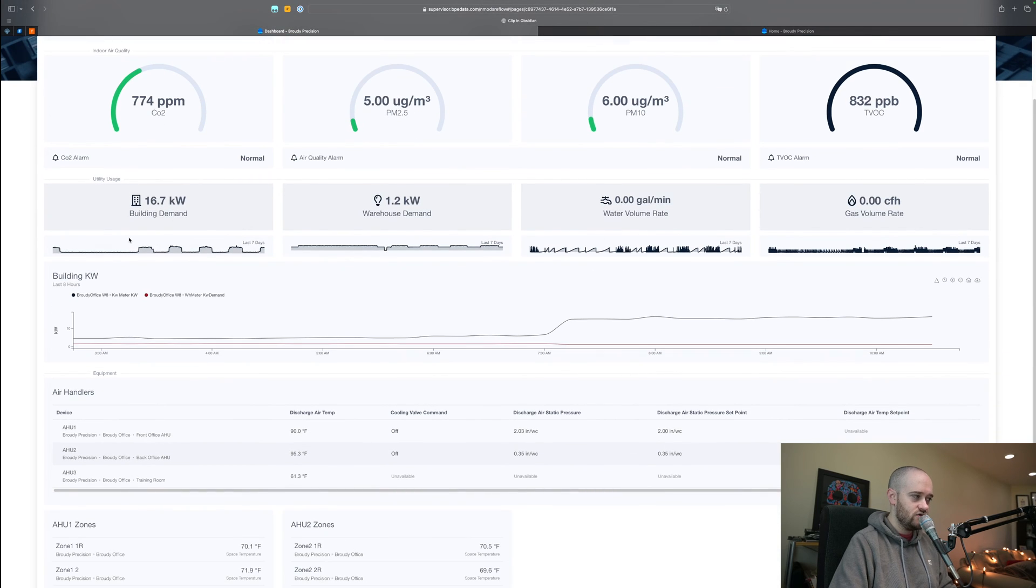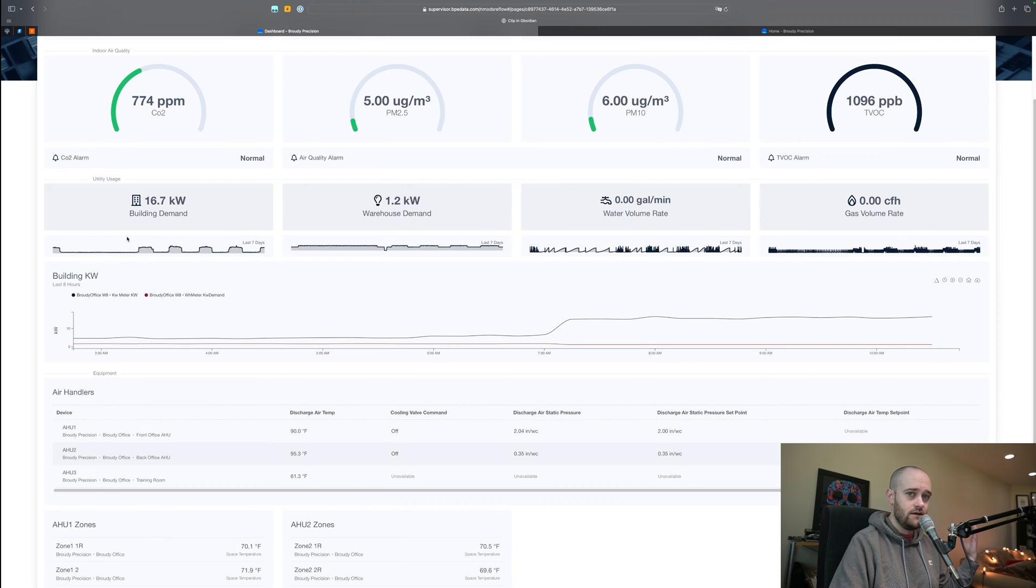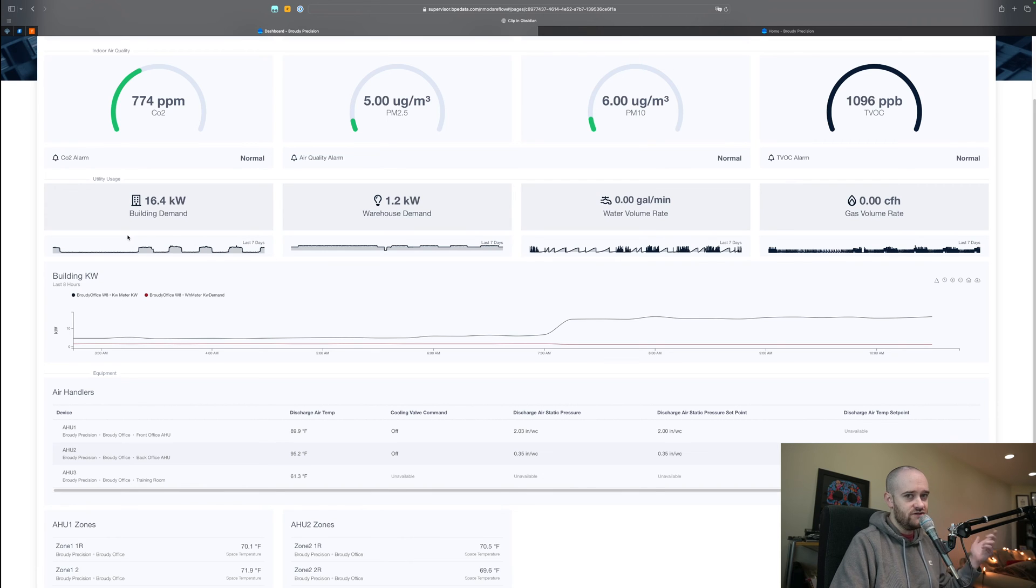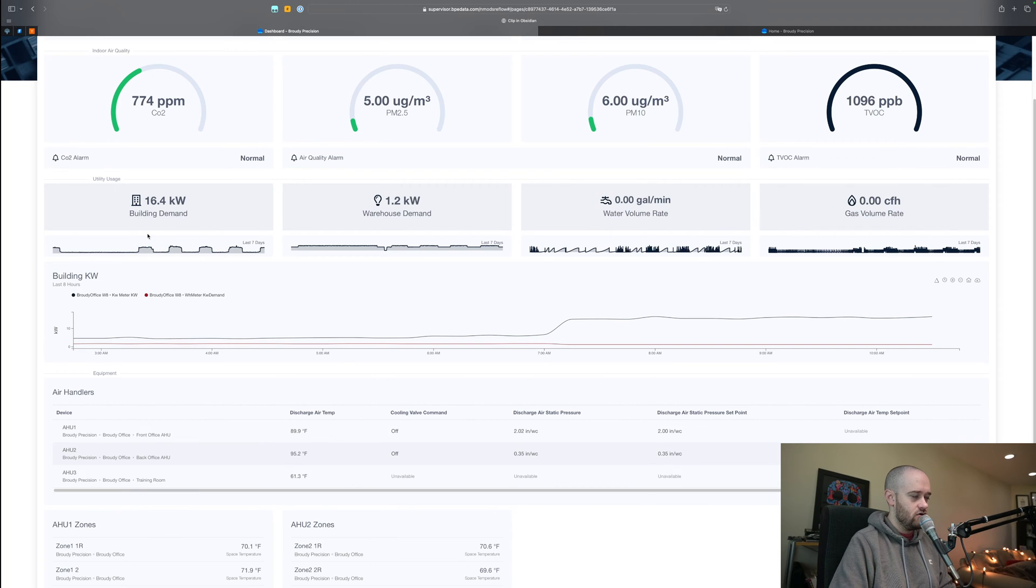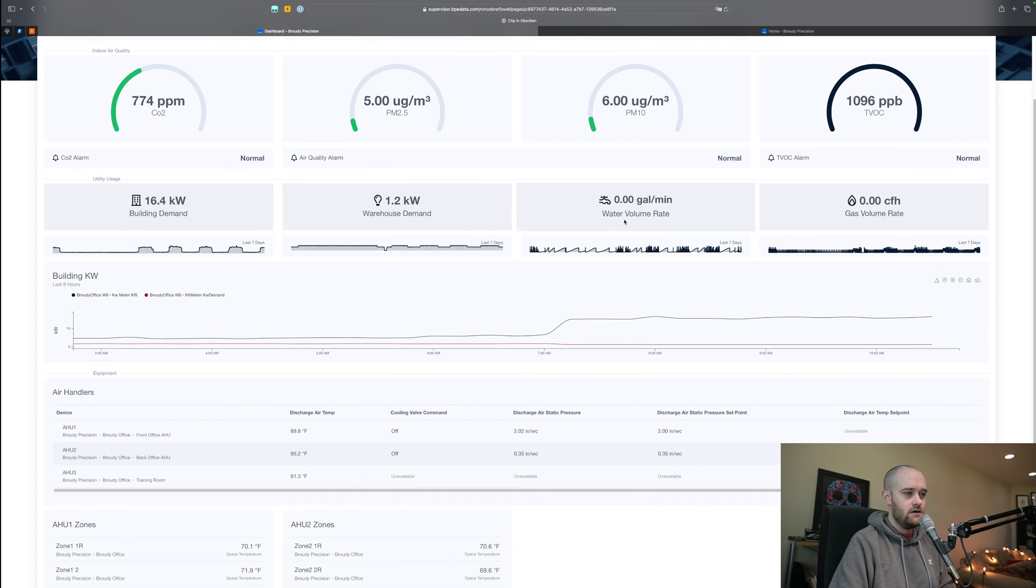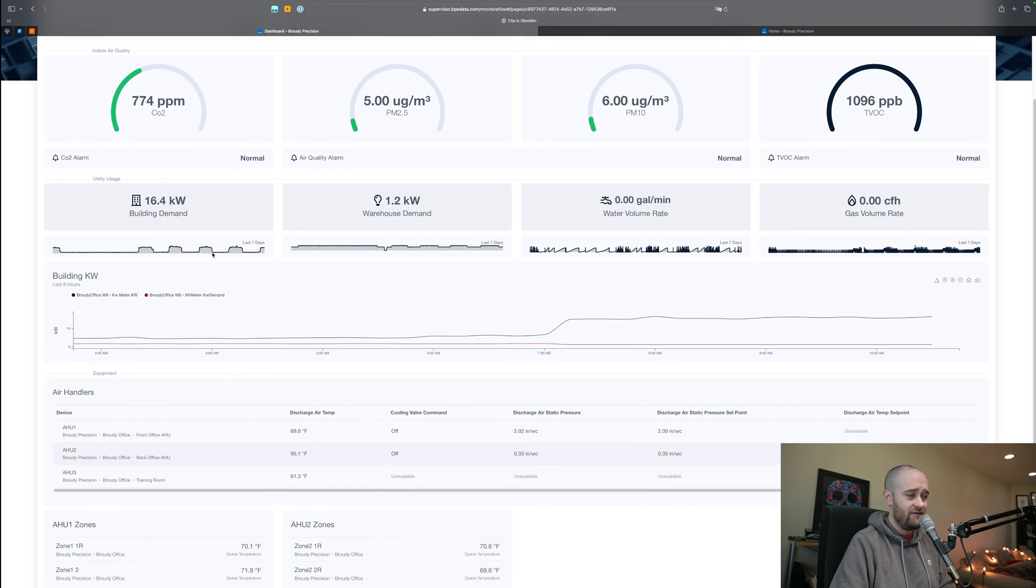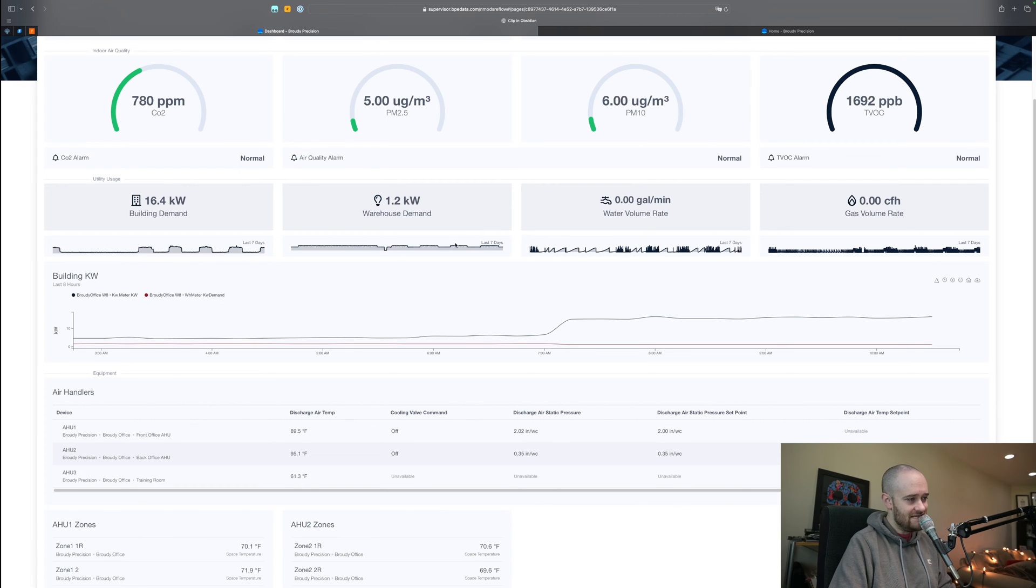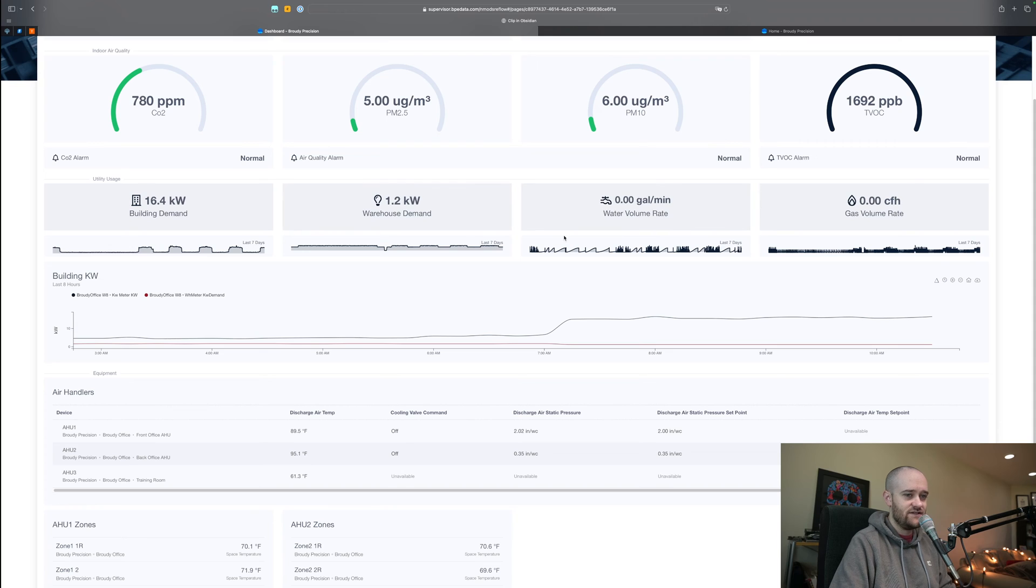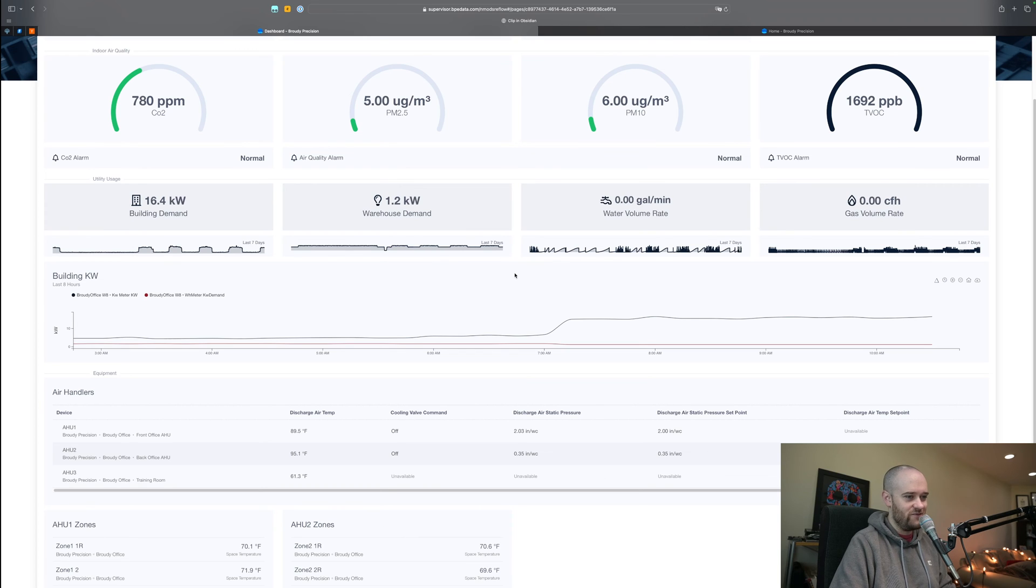Then we get into our utility usage over the last year. We've done a lot to bring in additional meters so that we can show off the kind of energy and utility that we're using for the building. We've got our overall building demand, our warehouse lighting demand, our water volume rates, how much water we're using, and how much gas we're using as well for heat. Underneath those we have a little bit of a sparkline chart which is a nice easy way to get a quick look at the last seven days worth of values, and you can pick up on problematic things in here very easily, like if lights get left on when they shouldn't.